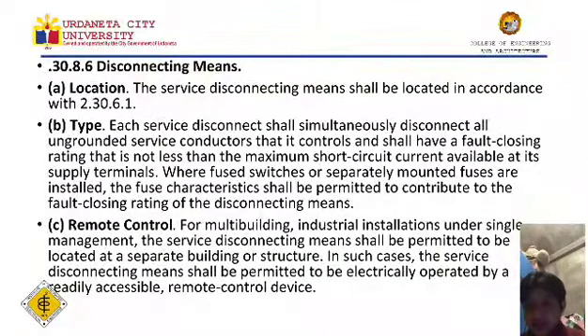And last part of disconnecting means is remote control. Remote control for multi-building industrial installation under single management. Service disconnecting means shall be permitted to be located at a separate building or structure. In such cases, the service disconnecting means shall be permitted to be electrically operated by a readily accessible remote or remote control device. Dito ulit sa remote control, ito na yung pwede mong ma-access, pwede mong makita dun, pinakamabilis na makita ba yun sa na room.